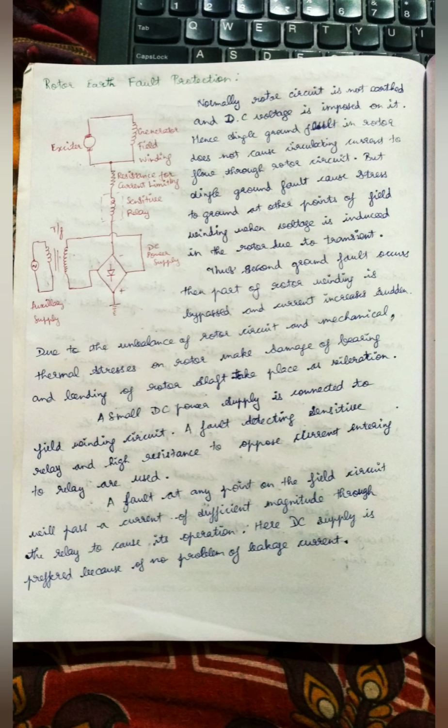But a single ground fault causes stress to the ground at other points of your winding, and when voltage is induced in the rotor due to this transient stress, the leakage tries to escape from one end to another end. So in this case, the fault may occur in various places of your rotor, and it will cause your winding to malfunction or suffer mechanical stress, and it will also damage your bearings, bend your rotor shafts, and cause vibration of your generator.